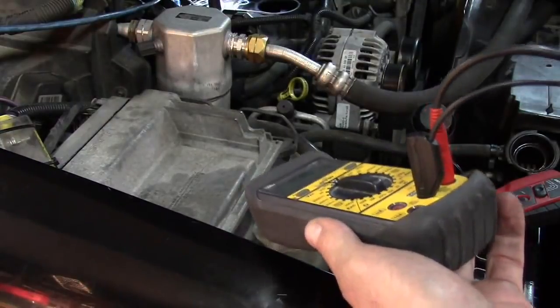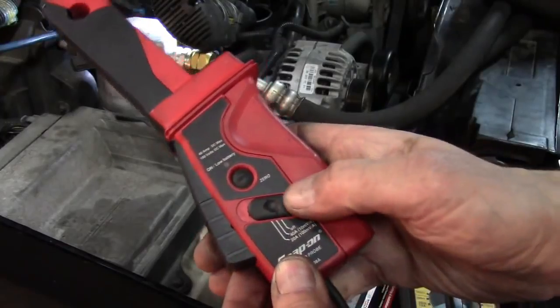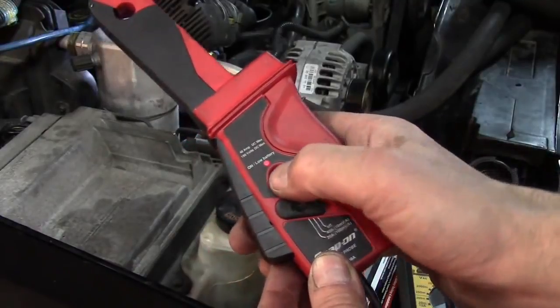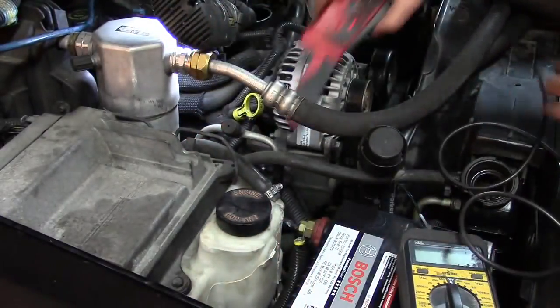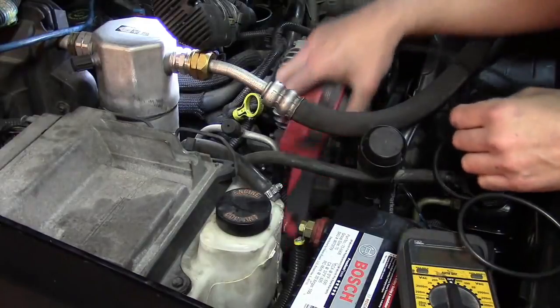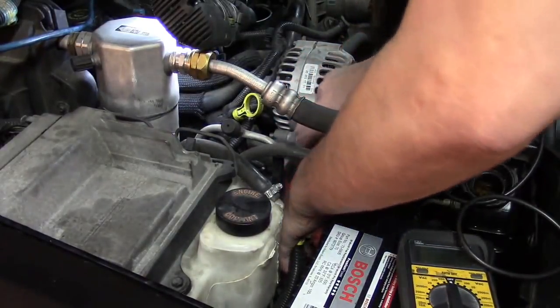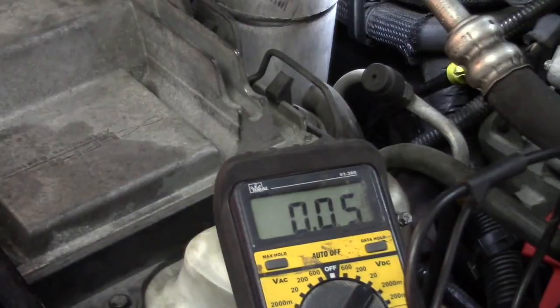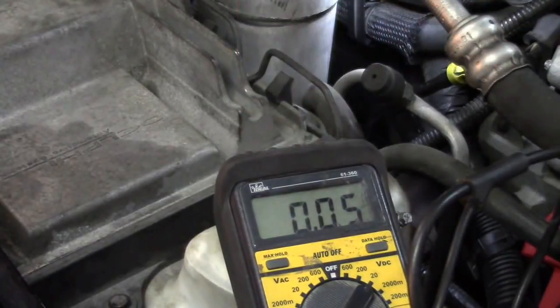So let's set this up and I'll show you how it works. You hook up the tool to your DVOM as if you're going to do a regular voltage test, then turn your probe on. I'm going to set it to the 20 amp setting and zero it, then loop it around the cable you're testing - in this case, the negative battery cable. I've got my meter set on the 20 volt scale, and you can see we're reading 0.05 - not 0.5, remember we're measuring volts, not amps. We need to multiply this result by 10 to get the number of amps, and when we do that, we get 0.5 amps.